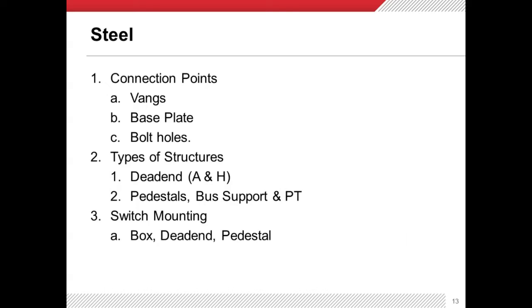One of the main ones is a dead-end structure. These are generally the largest ones. You may have them to terminate lines, or if you've got a big transformer bank, you'll put dead-end structures either over the transformers or just in front or behind them, because you're going to connect it with strain bus to the switch rack.